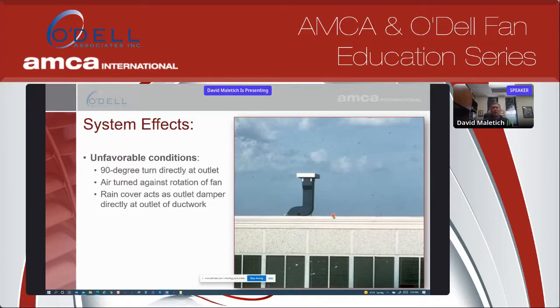I have no idea why they designed it this way. Top horizontal fan, position C elbow. Air deadheads here, has to get reaccelerated back out. This rain cap on the top deadheads the air again, has to be bent 180 degrees down. If this was an upblast fan, that would have been a significant improvement right there. And then if they put a no loss rain hood on top of that unit, that would further increase performance because we wouldn't have any losses associated with this appurtenance here.